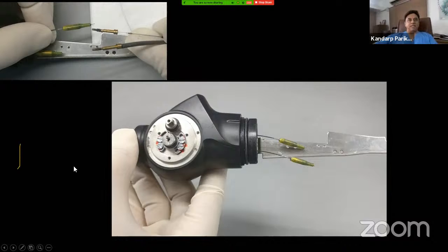So my advice is that whenever the deflection has deteriorated from 270-degree to 220 or 180, do not use that scope. Please give it for repair. They will simply open the handle and tighten these wires, and your scope is ready. So you will spend minimum money, and your scope is ready. Once you break this wire, they will ask you for a replacement.